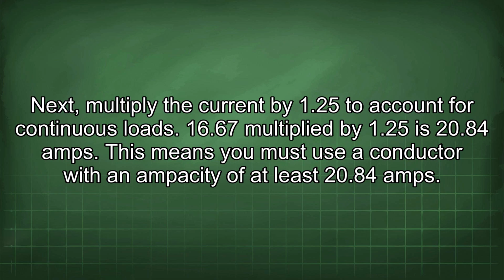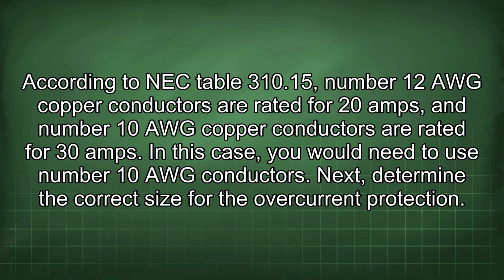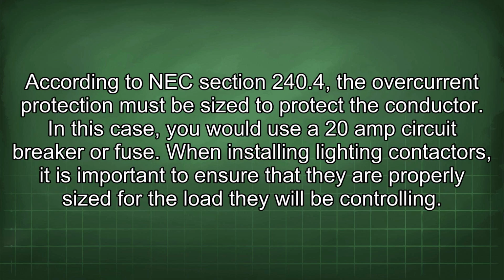This means you must use a conductor with an ampacity of at least 20.84 amps. According to NEC Table 310.15, number 12 AWG copper conductors are rated for 20 amps, and number 10 AWG copper conductors are rated for 30 amps. In this case, you would need to use number 10 AWG conductors. Next, determine the correct size for the overcurrent protection. According to NEC Section 240.4, the overcurrent protection must be sized to protect the conductor. In this case, you would use a 20 amp circuit breaker or fuse.